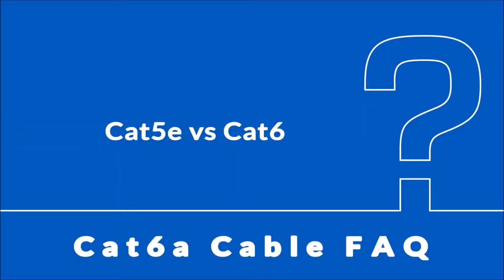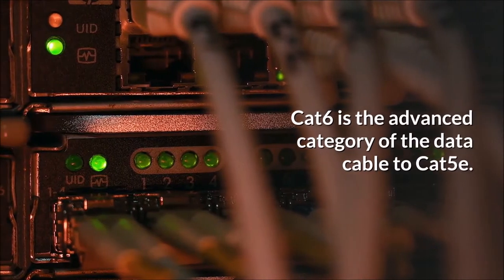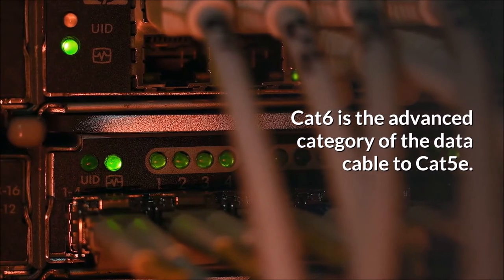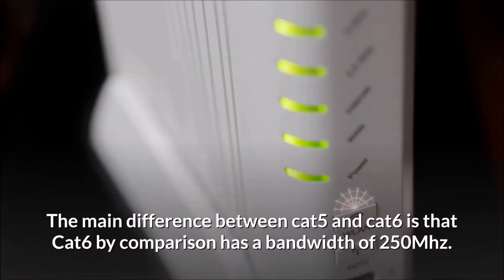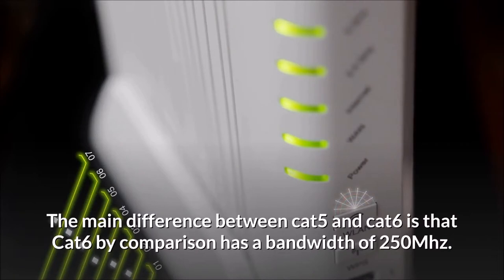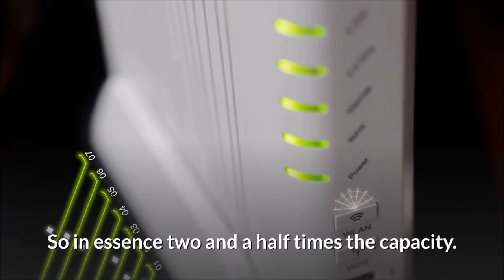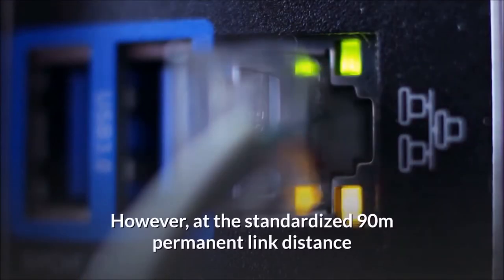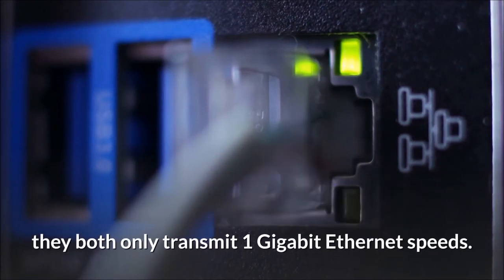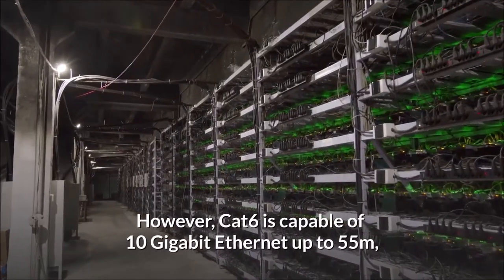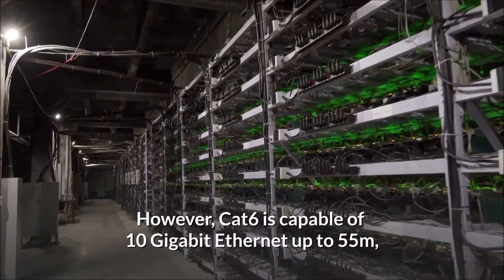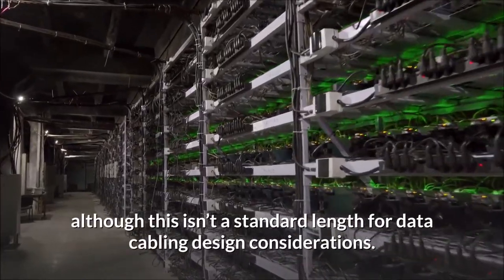Cat5e versus Cat6. Cat6 is the advanced category of the data cable to Cat5e. The main difference between Cat5e and Cat6 is that Cat6 by comparison has a bandwidth of 250 MHz. So in essence 2.5 times the capacity. However, at the standardized 90 meters permanent link distance they both only transmit 1 gigabit Ethernet speeds. However, Cat6 is capable of 10 gigabit Ethernet up to 55 meters, although this isn't a standard length for data cabling design considerations.